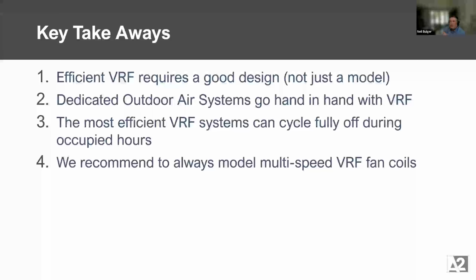it can somewhat be seen in the IEER metric, but again, in the model, we're really using the full load efficiency and just assuming those curves represent the right part load. If we really have poor controls, you'll almost see the system run at flat efficiency. So if you have controls configured at set heating and cooling set points for the compressor, it'll just be 11 EER forever. So that's where you might end up having a model that says you should get savings. You might find your field site missed that toggle and it's not getting the savings they expected. So it can be a tricky system for sure.